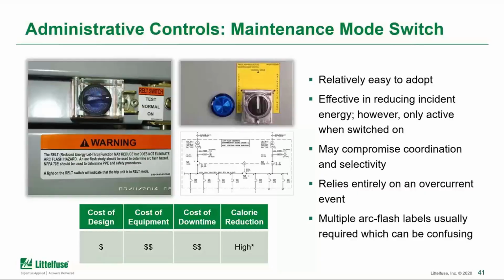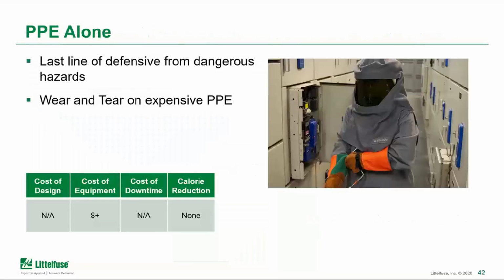The calorie reduction is also fairly high. So that is something that, when this maintenance mode is switched on, is quite effective in reducing the incident energy. But again, one important caveat is that it does rely on human intervention for somebody to engage the maintenance mode switch. And finally, we talk about PPE a lot as a key part of this.